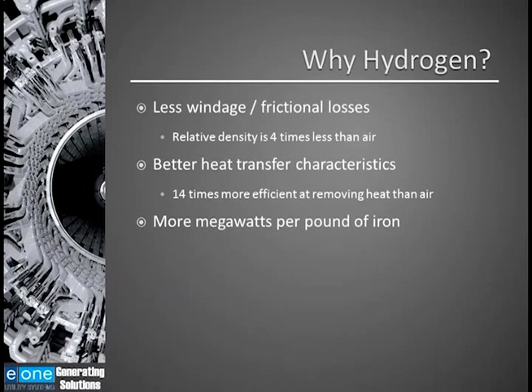Why hydrogen? Because it takes less horsepower to produce more power. Hydrogen has less windage and frictional losses. The relative density of hydrogen is 4 times less than air. What this means is that you can spin the rotor in the generator a lot easier when it's surrounded by hydrogen versus air. Hydrogen has better heat transfer characteristics. Hydrogen is 14 times more efficient at removing heat from components in the generator that are heating up. The bottom line is you get more megawatts per pound of iron by using hydrogen as a cooling medium.